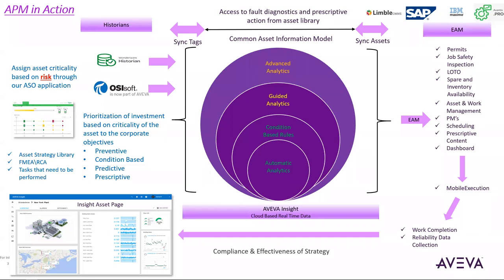And then if we have what we call, along the guided analytics, a poor anomaly score for the asset that we put in a filter, 85 or higher, okay, it presents itself in the newsfeed again, saying, hey, we're looking at these points on this asset over this time frame. We call it a catch. Say, Michelle, we're not sure, but we want to bring your attention to a potential problem because we think that this is starting, you know, early days of a potential problem. And why that's important to customers, they say it costs you folks 3 to 5 times more money to fix something once it's broke than an early warning. And that's what it is in the newsfeed.